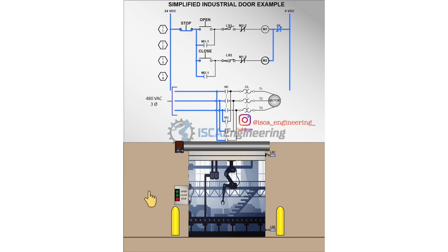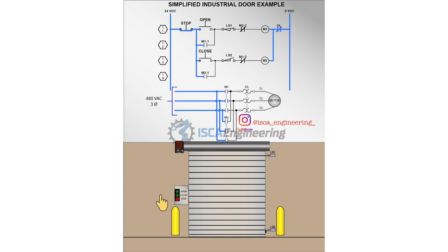The same concept is used to bring the door down. Pressing the down button will energize the second motor starter and reverse the rotation of the motor in order to bring the door down. After the door has reached its limit and actuated limit switch 2, the limit switch will open and stop current from flowing to the motor. The stop button can be pressed at any time whenever the door is going either up or down to stop the current from flowing to the motor. If both the up and down buttons were to be pressed at the same time, then the door would not move at all.